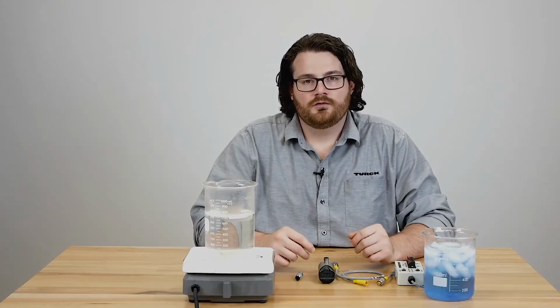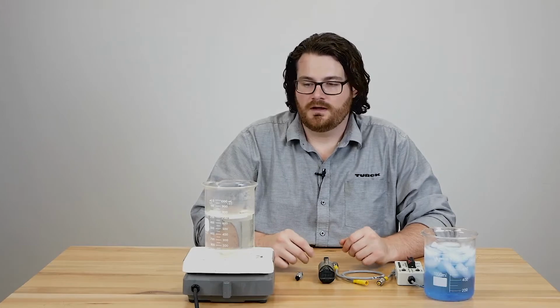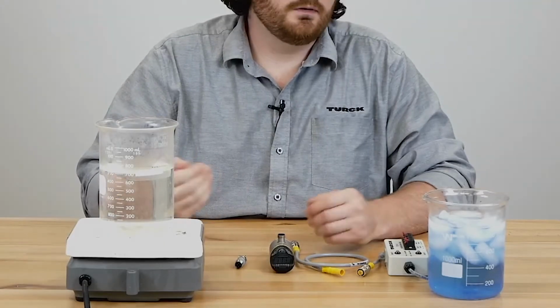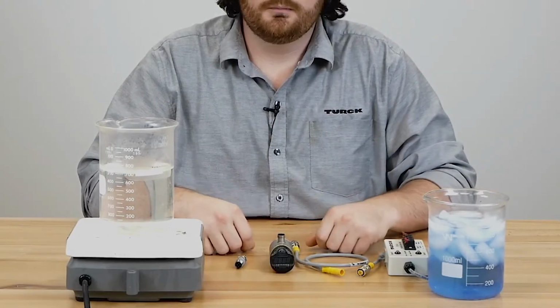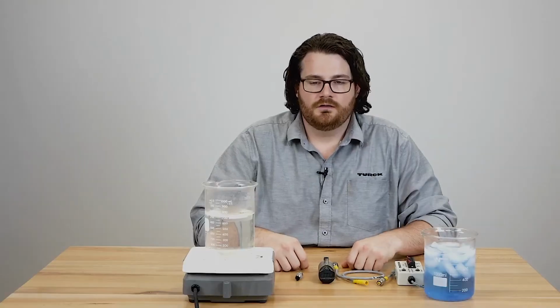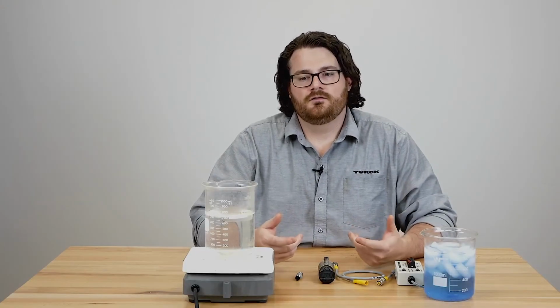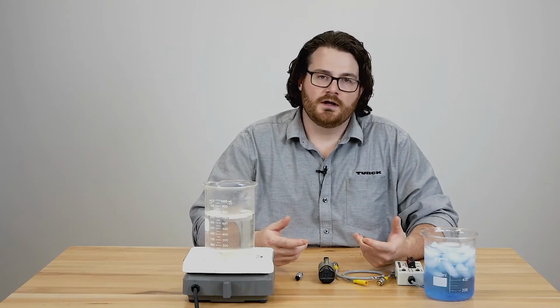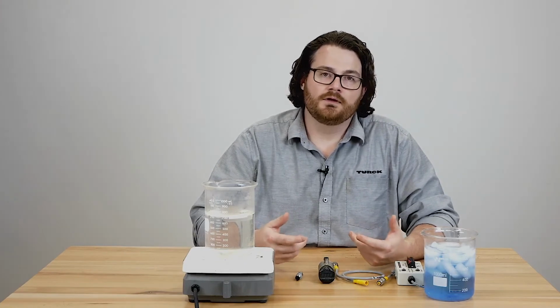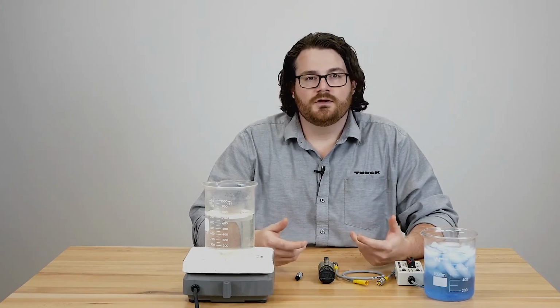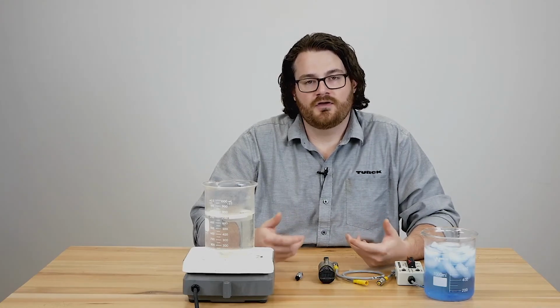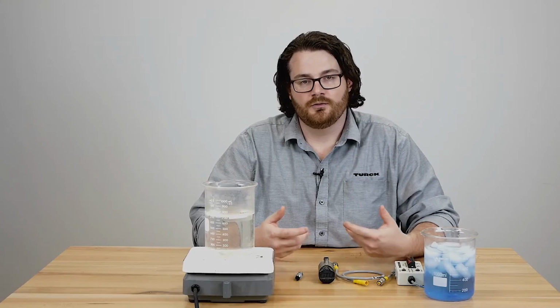We will use this sensor to monitor a hypothetical process application using 1 beaker of hot water and 1 beaker of cold water to simulate temperature extremes. For the sake of this hypothetical, let's say that the process needs to stay between 30 and 80 degrees Fahrenheit, otherwise an alarm output gets energized. Additionally, we're going to program the LED to change red when the temperatures are outside of these limits as a visual indication to an operator.